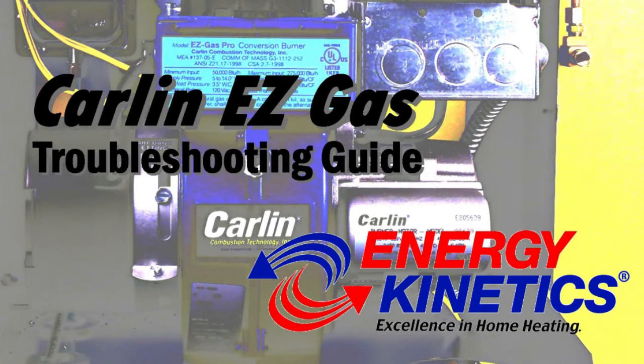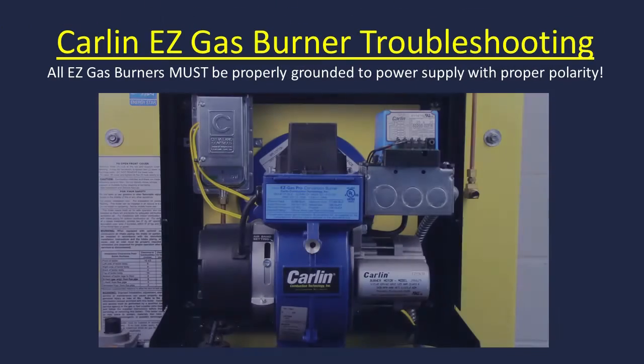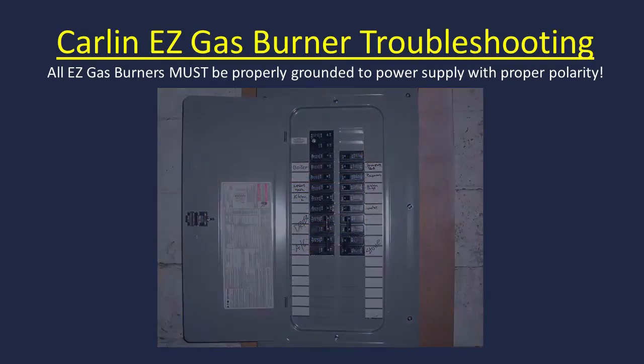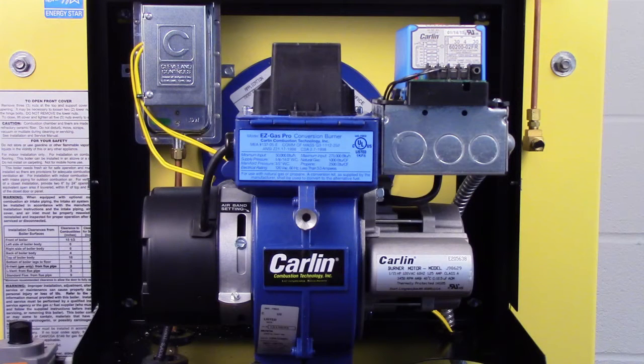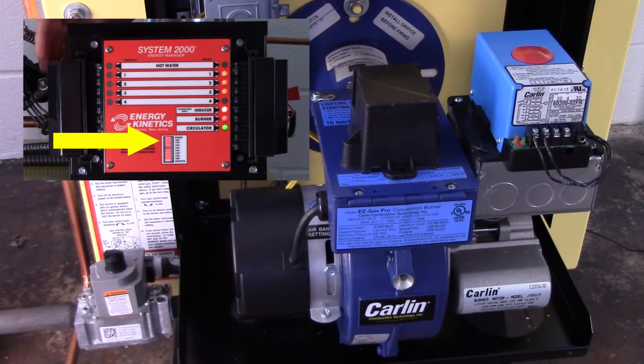Welcome to the Carlin EZ Gas Troubleshooting Guide. Remember, for safe and dependable operation, all EZ Gas burners must be properly grounded back to the power supply panel and have correct polarity. Before we begin troubleshooting, let's walk through a normal burner cycle so we know what to look and listen for. Self-test 1 is performed each time power is applied to the primary control.